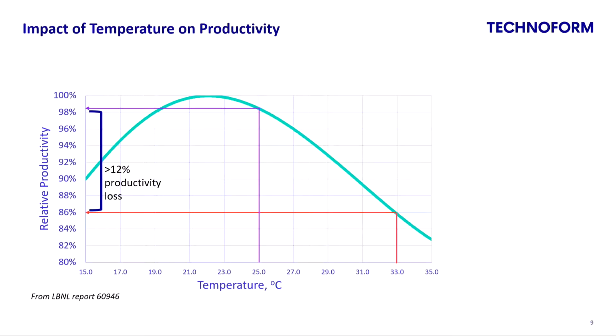This graph, the line in green, shows you the relative productivity as a function of temperature. Studies have shown that if you're between about 71, 72 degrees Fahrenheit, around 21 degrees Celsius, that's optimum for productivity. Every degree Fahrenheit or degree C that you go outside of that range, either higher or lower, hotter or colder, you lose about 1% of productivity.